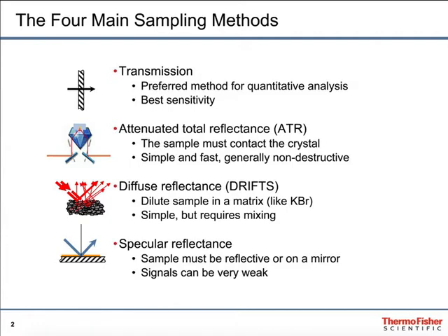In diffuse reflectance, the IR beam interacts with a sample which is in a loosely packed powder, usually mixed with an inert ingredient such as KBr or diamond powder. In specular reflection, the IR beam passes through a sample which is on the surface of a reflective sample, strikes the reflective surface, and then bounces back through that sample a second time — double passing — and then goes onto the detector. Each of these techniques has relative strengths and weaknesses for specific sample types, and we'll briefly examine those.